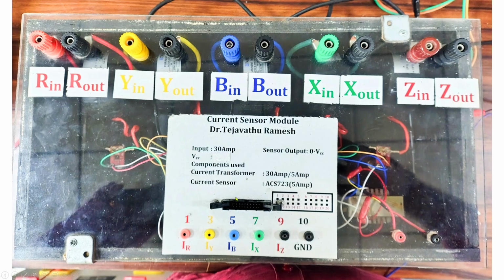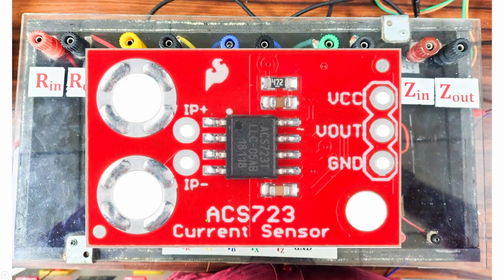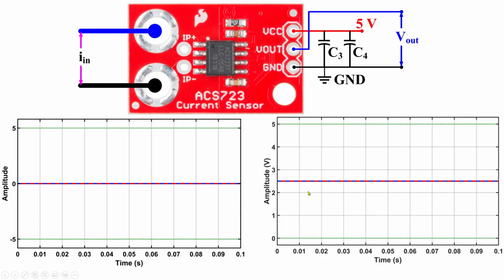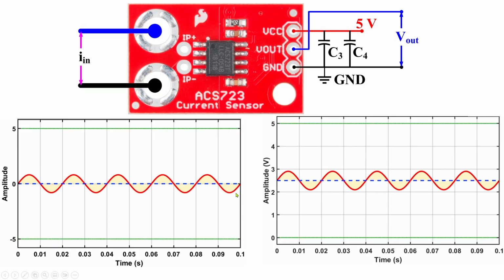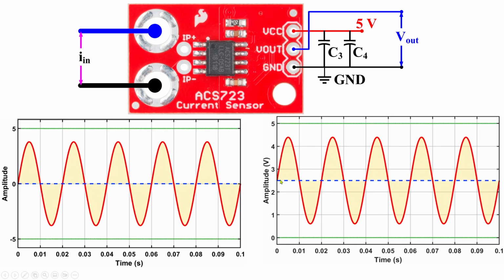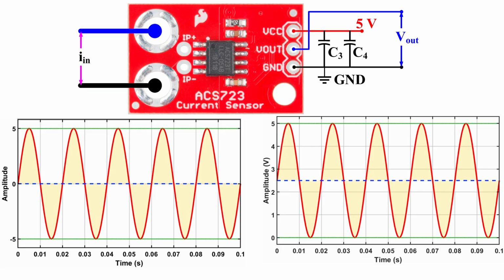In this current sensor module, I am using a 5 ampere bidirectional ACS723 current sensor. When there is no current, the sensor output stays around 2.5 volts. As the input current amplitude increases, the output voltage also changes more clearly. One important point is that the output waveform is not centered around 0 - it is shifted around 2.5 volts. Because of this offset, the complete AC current waveform is converted into a positive voltage signal within the 0 to 5 volt range. So the ACS723 output voltage can go up to 5 volts.